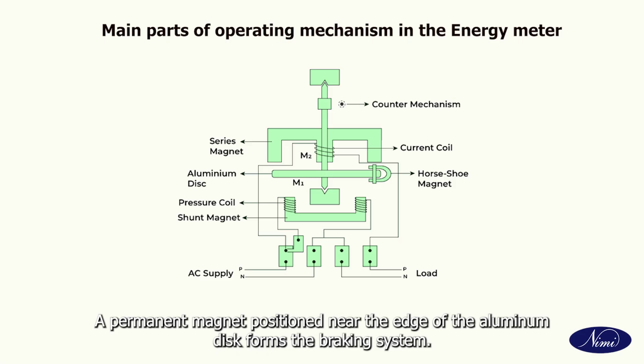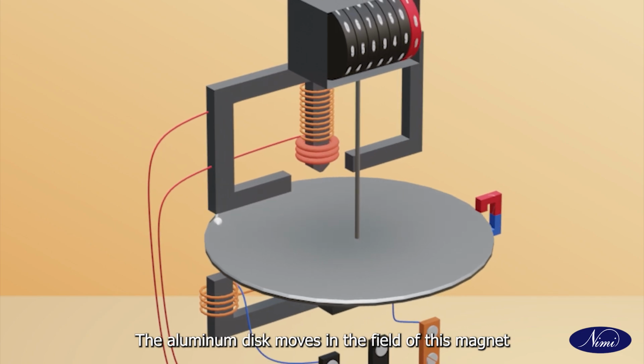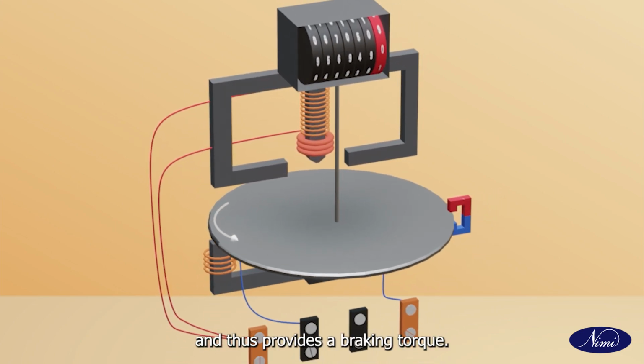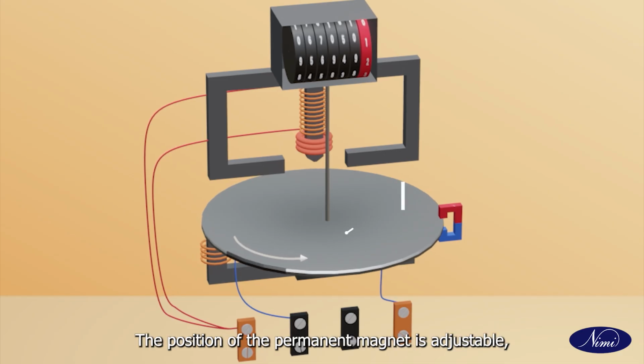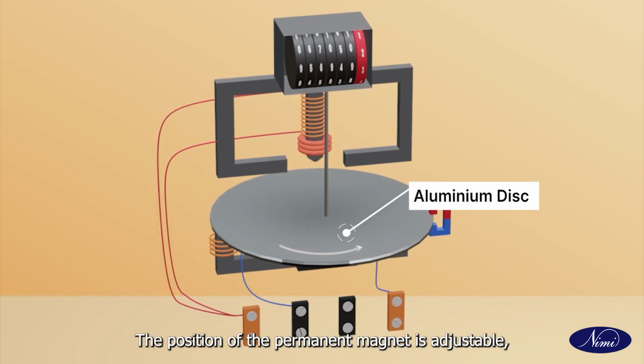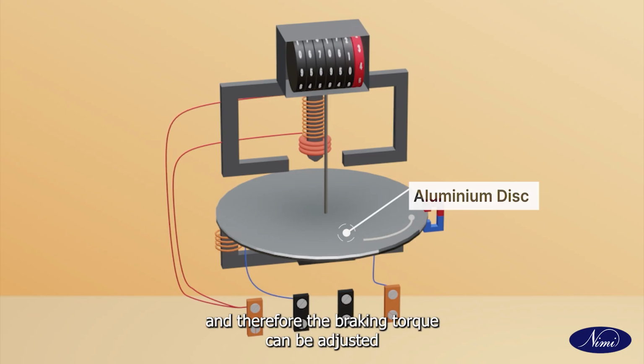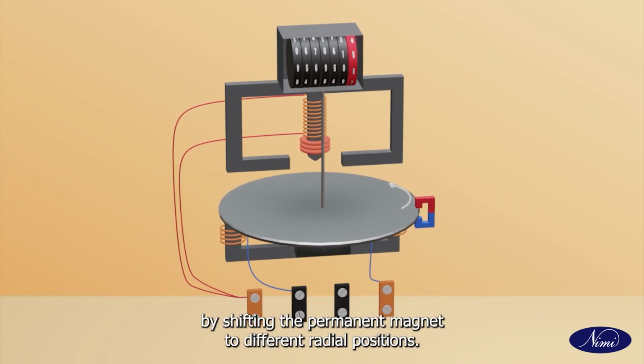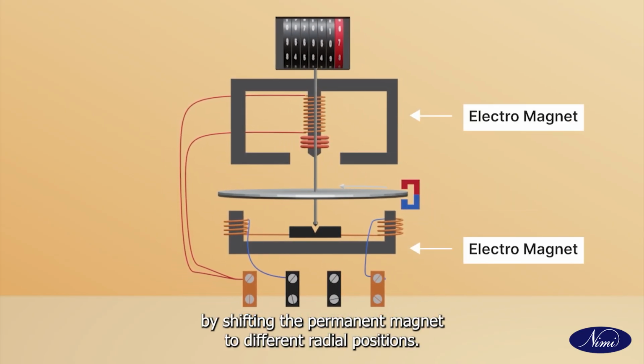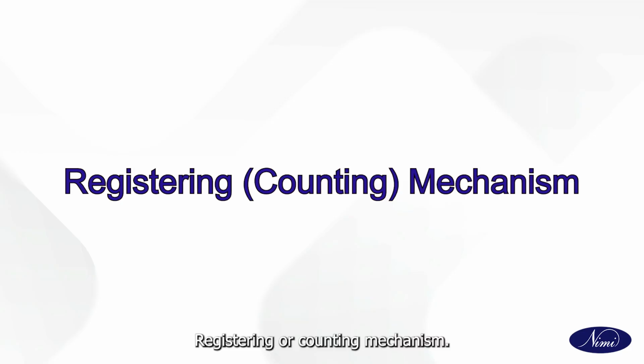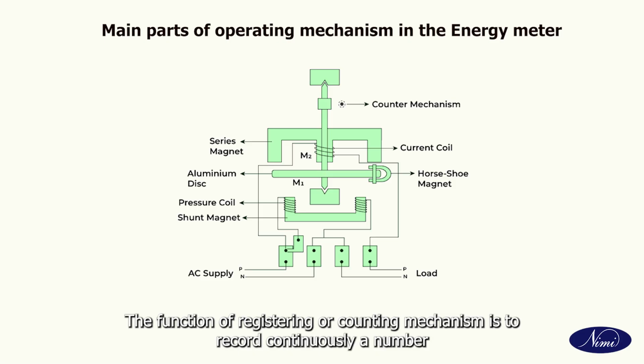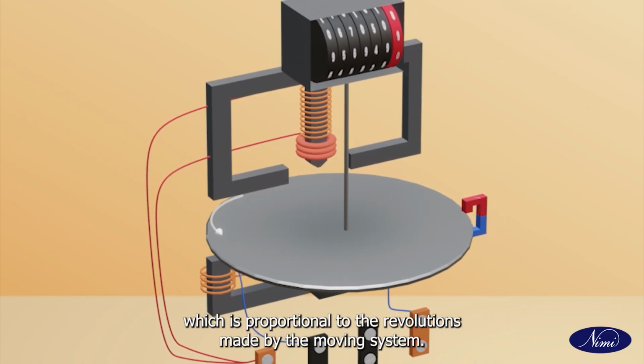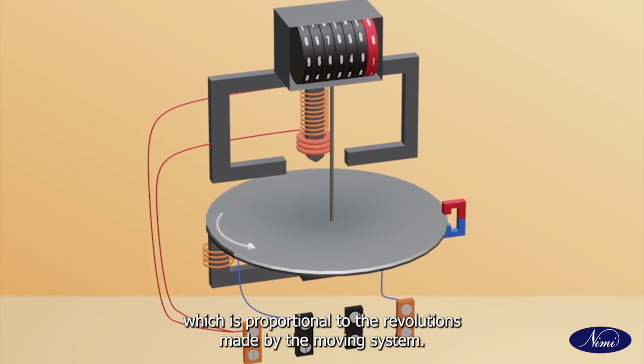Braking system. A permanent magnet positioned near the edge of the aluminum disc forms the braking system. The aluminum disc moves in the field of this magnet and thus provides a braking torque. The position of the permanent magnet is adjustable and therefore the braking torque can be adjusted by shifting the permanent magnet to different radial positions. Registering or counting mechanism. The function of the registering or counting mechanism is to record continuously a number which is proportional to the revolutions made by the moving system.